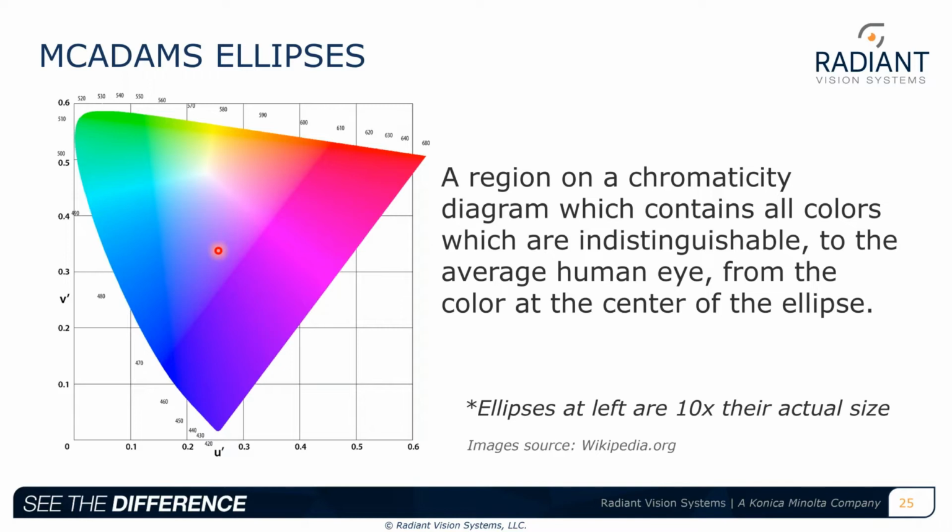Part of the reason this was done is to make the chart a little more fair. So now if you're talking about a change of 0.01 in CX, CY, it actually has more meaning, and we'd see this much noticeable difference. So whichever chart you use is really industry dependent. Some are willing to go to the U prime and V prime. Others, for standard reasons, are using the 1931. But at its core, they're really the same thing because they have the same tristimulus X, Y, and Z values. And from there, it's just math to compute the coordinates.